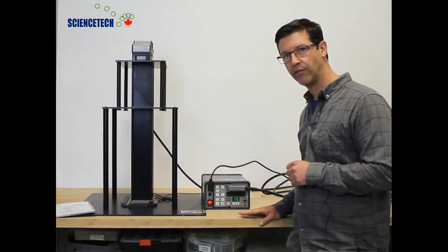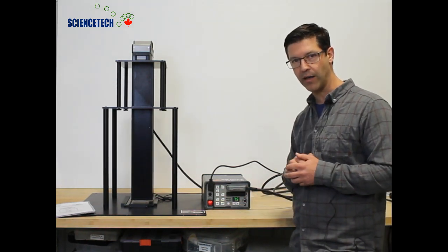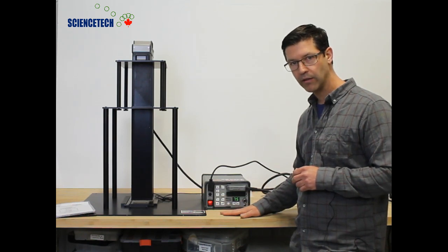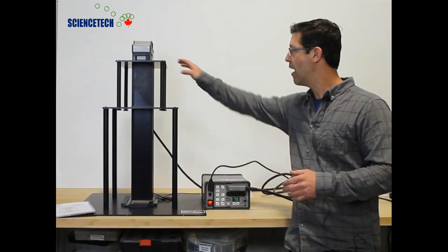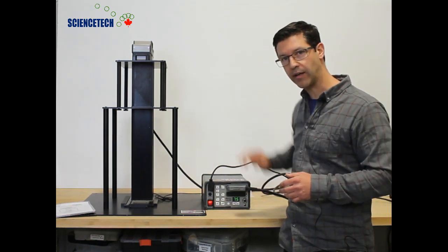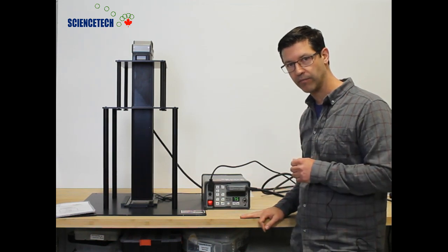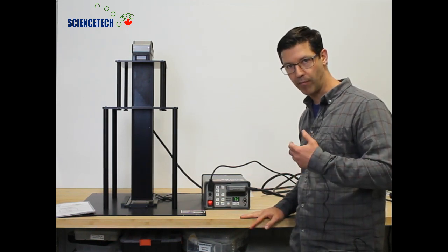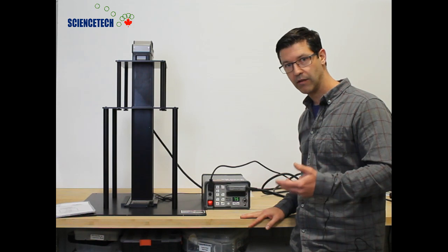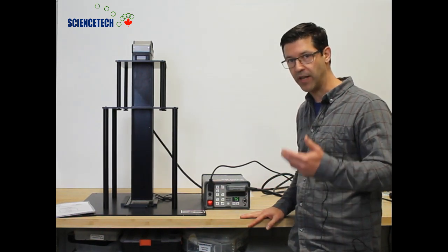When we flash at 7.5 on the power supply, we have to wait a minimum of 110 seconds in between flashes. If you flash at a rate higher than that, there is a risk that you will damage the instrument.